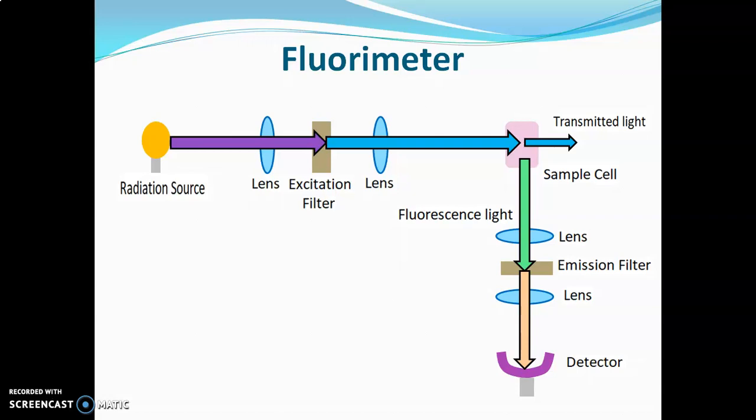The detector is kept at 90 degrees to the radiation source because if it were kept in a straight line at 180 degrees, the transmitted light would interfere with the fluorescence light and give wrong results. To avoid this interference, the detector is kept at 90 degrees to the radiation source.